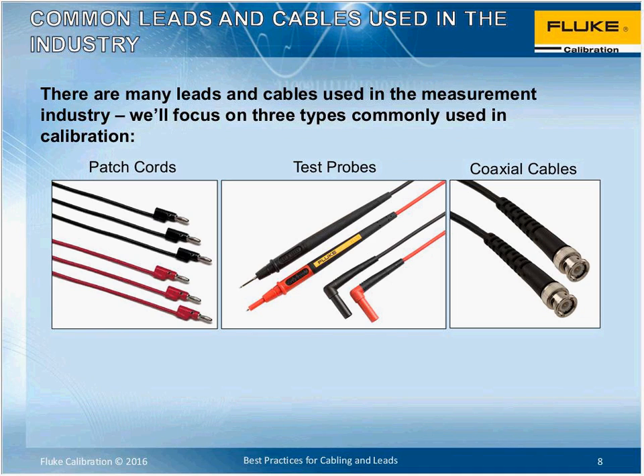I'm going to cover 3 types of common cable leads here, just to give us a basis as we talk through the recommended measurements. The first one is patch cords. Patch cords are typically used for either calibrator to DMM connections or calibrator to calibrator connections, or even in some transfer measurements. Basically, they have the same type of connector on both ends, such as spade lug or banana. It's a way to connect 2 instruments together.